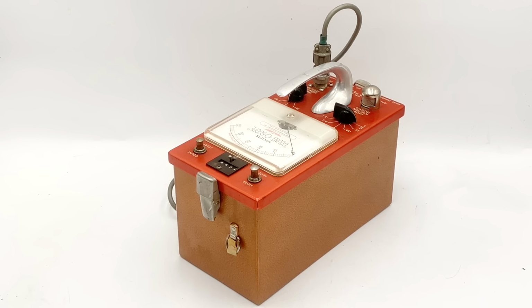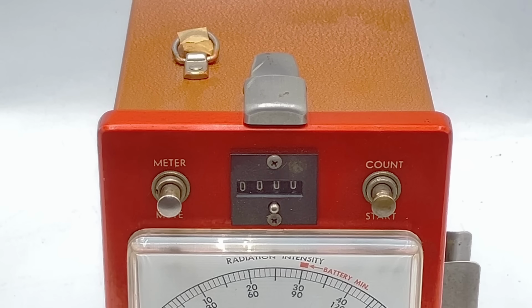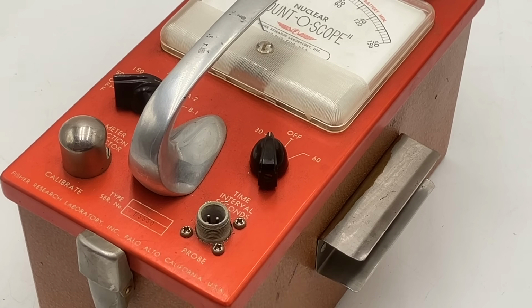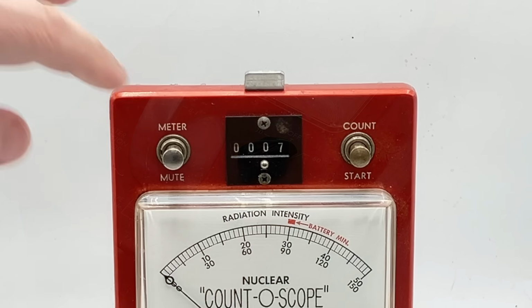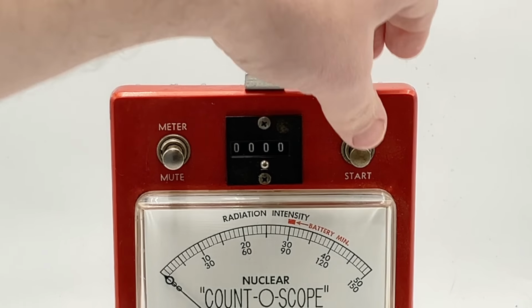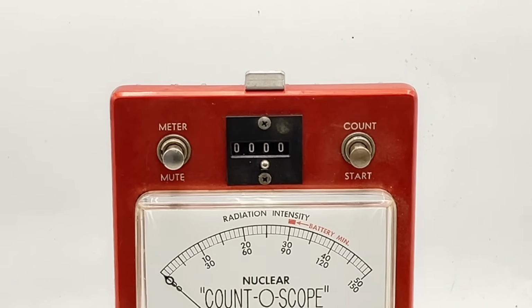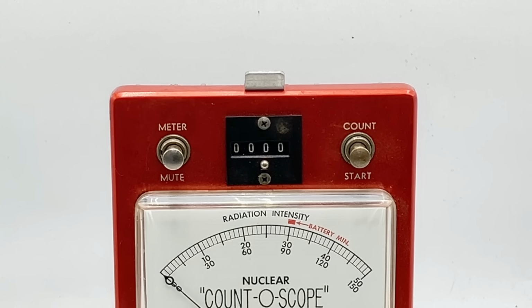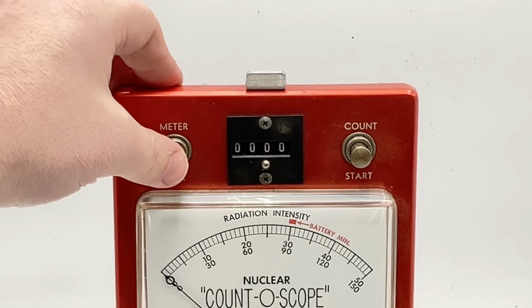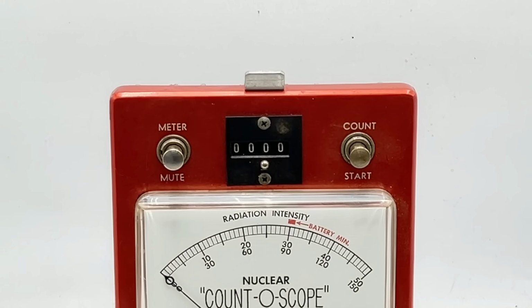Other than the scaler, there are no other output devices on this unit: no neon flasher, speaker, or headphones, so unfortunately this cannot produce the iconic Geiger counter chattering noise. And finally, at the top we have our 4-digit scaler, which, as I mentioned previously, counts up the number of radioactive particles detected over a 30 or 60-second period. To use this, you set the right-hand knob to either 30 or 60, reset the scaler by throwing this little lever, then press the Count Start button on the right. The scaler will automatically stop counting when the selected time interval has elapsed. If desired, you can also push the meter mute button to shut off the readout dial.